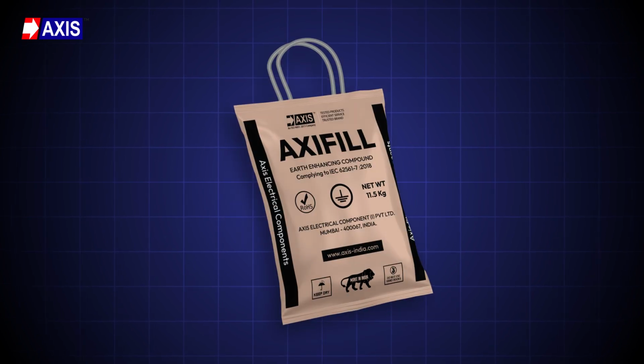Secondly, Axifill. This is a highly conductive earth enhancing compound, ideal for locations where low earth resistance is critical. It is bentonite based like Axifill-lite, but has special minerals and moisture absorbing agents. These include compounds of sodium, calcium, magnesium, and potassium, which improve conductivity and help retain moisture over time. Its resistivity is 0.12 ohm meters, making it suitable for sensitive electrical systems.